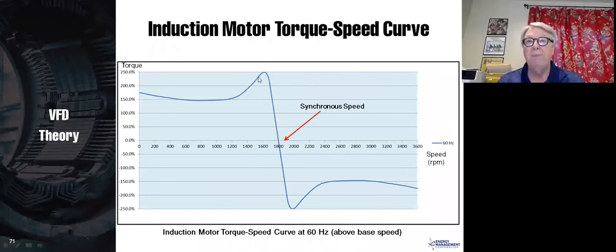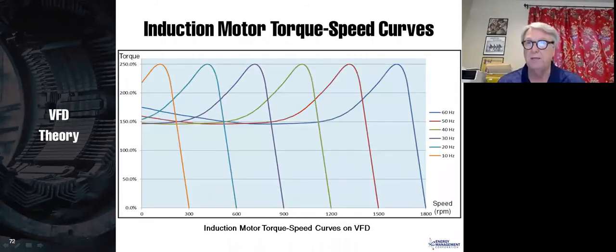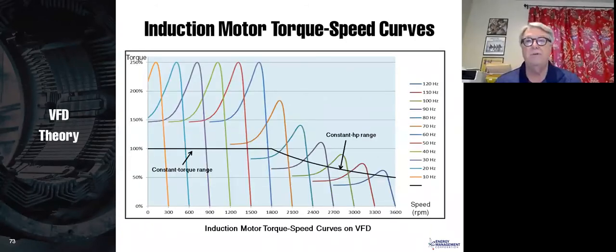If you go above base speed, then you basically just get a mirror image of that. Now on a variable frequency drive, if you're at 60 hertz, you get this curve that gives you 1800 RPM. If you're at 50 hertz, you get this curve that gives you 1500 RPM and so on. So we're always operating on this portion of the torque speed curve. And when we just gradually increase the speed of that motor, it's always running. It never actually starts.